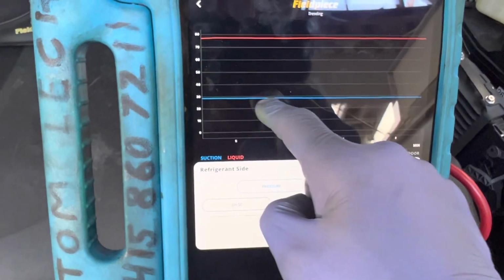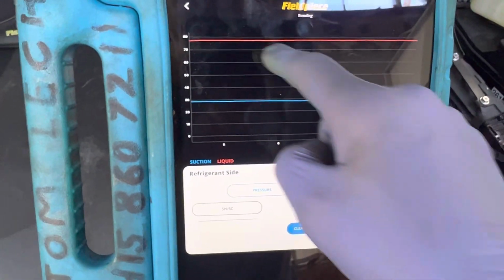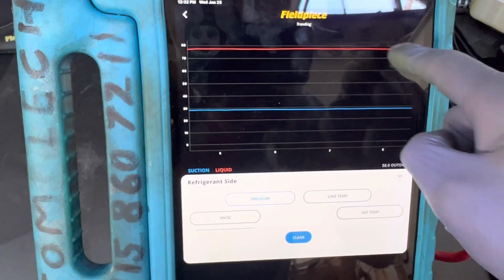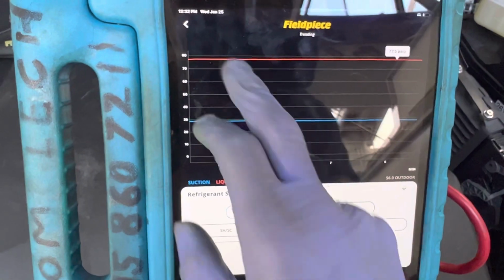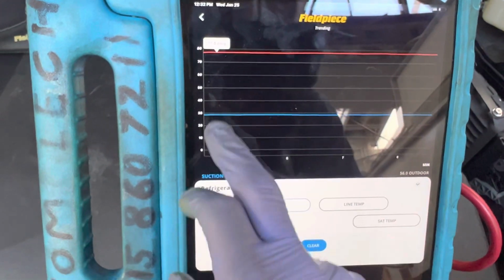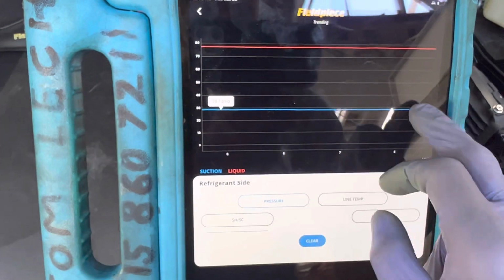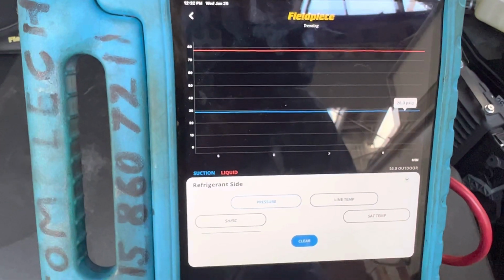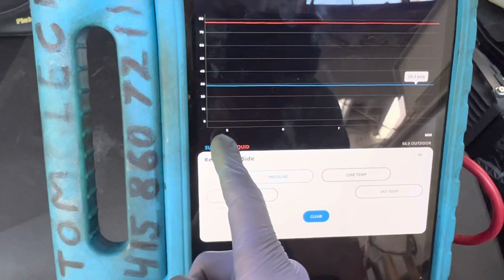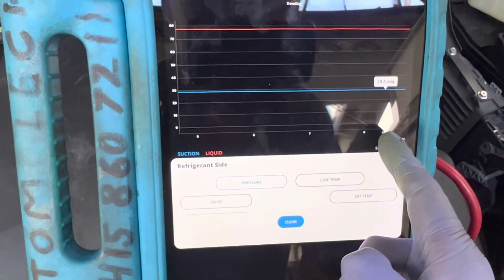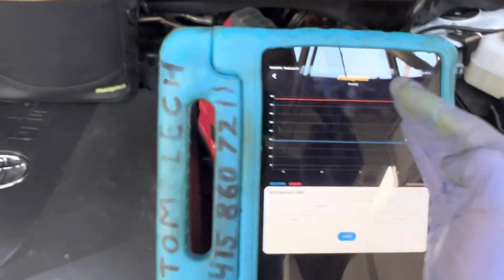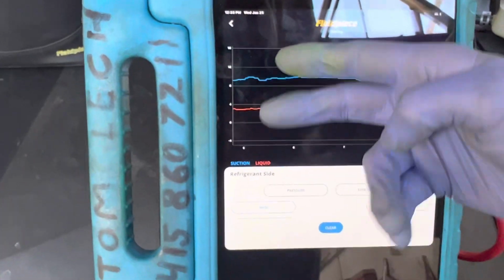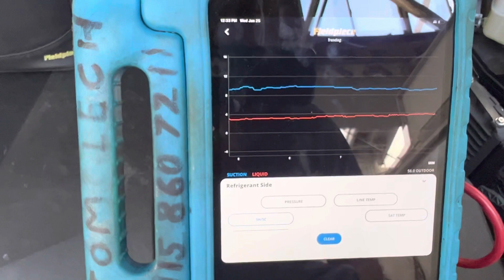Let's look at how this has been tracking. Look at how steady these temperatures and pressures are. Absolutely no movement within about 1 PSI. 77 there, 77 there, 28.7 there, 28.3 there. That's over a period from minute 5 to past minute 8. Absolutely rock steady, no movement at all. We look at our superheat and subcooling, just tiny variances.